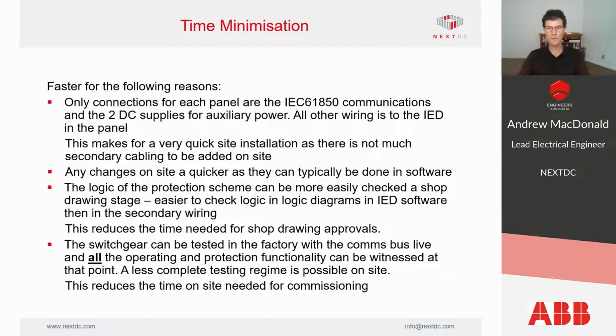It makes for very quick installation on site, as there's not really much wiring for the contractors to link up on site between panels. It also means that any changes on site are typically done in the logic in the IEDs or the other devices, which makes it quicker to make changes to the protection scheme if we have to, rather than having to rewire panels.